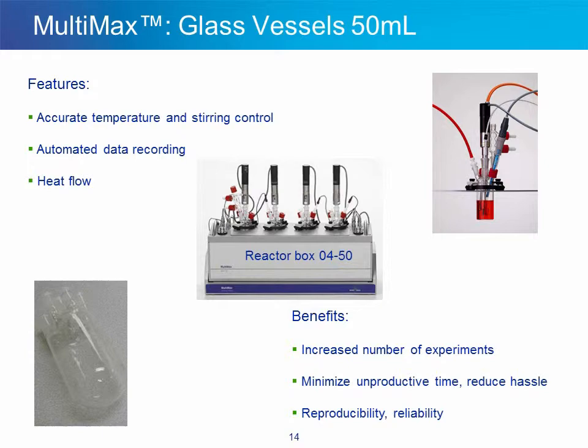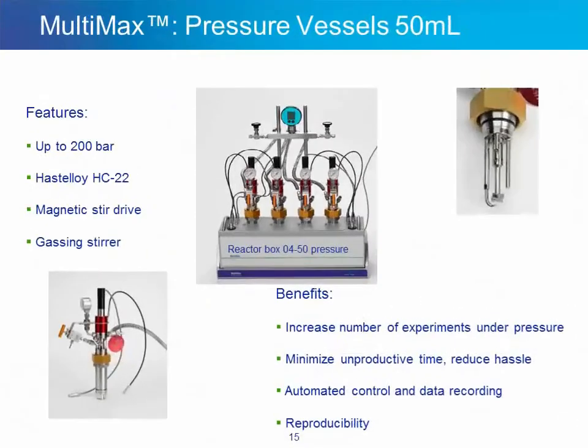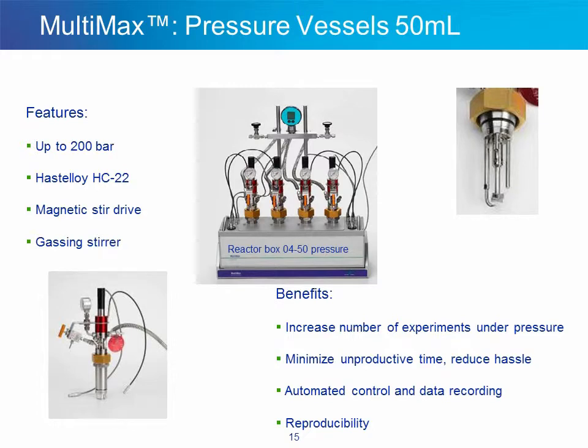Taking a closer look at the 4 by 50 mL vessel system: it offers very accurate temperature and stirring control with several impeller options, automated data logging and parameter control, and calorimetry is also available. The same Multimax technology and equipment allows to accommodate pressure vessels. They are made out of Hastelloy HC-22 and can stand pressure up to 200 bar. These vessels feature a magnetic stir drive and are outfitted with a gassing stirrer. Pressure control can be either fully manual or fully automatic in each individual vessel using a pressure controller.